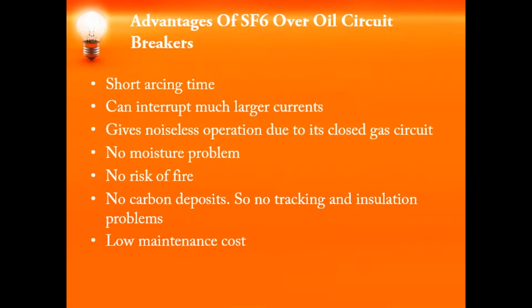There are also a few advantages of SF6 circuit breakers over oil circuit breakers. First, there is no risk of fire, and since carbonization doesn't form, there is no need to replace the SF6 again and again, and it can be used to interrupt very heavy currents. Whereas in oil circuit breakers, since the oil is present within a closed chamber, we need to watch the pressure maintained within the tank, and they cannot be used to interrupt very large currents. SF6 can interrupt very large currents, and there is no risk of moisture. The arcing time is also very short, the operation is noiseless, and less maintenance is required for SF6 circuit breakers.